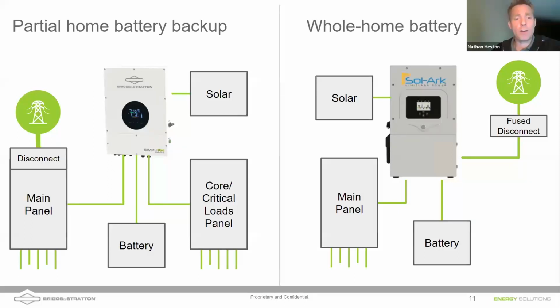It also requires the installation of what's called a critical loads panel or a backed up loads panel. These are loads that when the grid goes down, you still want to maintain access to. You might not need to have the washer and dryer. You might not need to have everything in your home on backup, but you'll probably put your lighting in there. You'll probably put your internet connection on there, possibly your television and other things that you want to keep on during an outage. But notice the difference on the right side of the screen. On the right side of the screen, the main loads panel is the only loads panel that's there. And so the right side is that whole home backup option, right? It's backing up all the loads in your house.